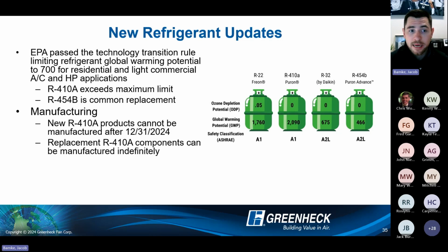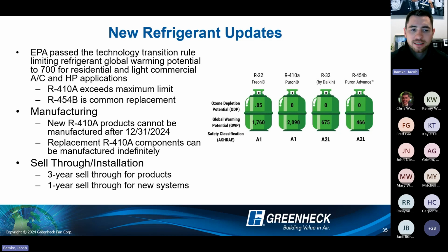So manufacturing, what does this mean from a date? For us specifically, new 410A equipment cannot be manufactured after December 31st of this year. So we're about 7 months away or so that we have to start transitioning this over. And with that said, if you're still purchasing equipment today or laying out 410A equipment, the replacement components can be manufactured indefinitely. So similar to R22, still going to be able to replace those components in the field. And then there is some sell-through and installation requirements as well.